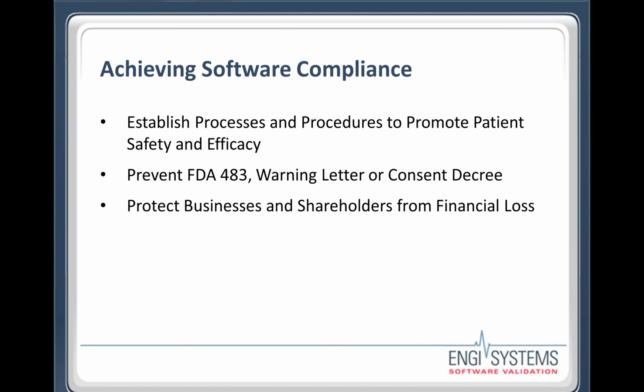What is the advantage of achieving software compliance? Well-established processes and procedures promote patient safety and efficacy, prevent FDA 483 warning letter or consent decree, protect business and shareholders from financial loss. Addressing an FDA 483 warning letter or consent decree is disruptive and expensive, especially if it requires the retrospective validation of an automated process, system, piece of equipment, or medical device software.